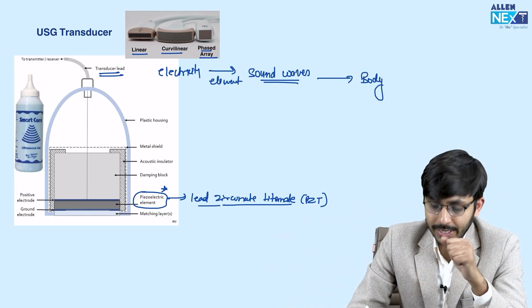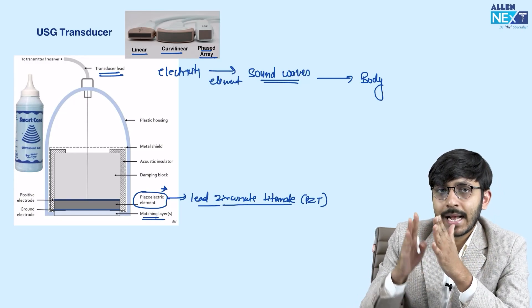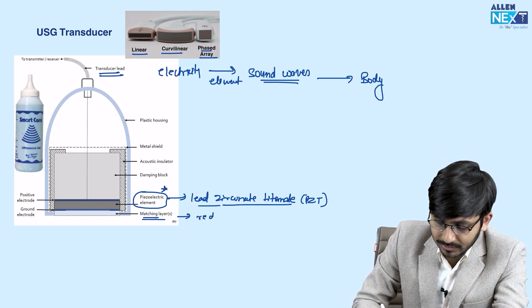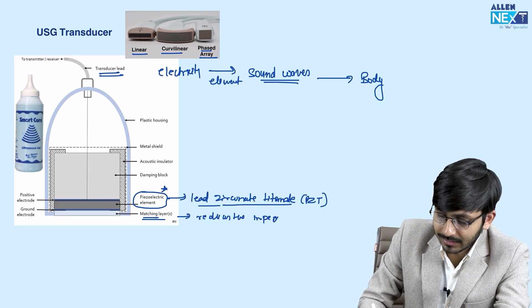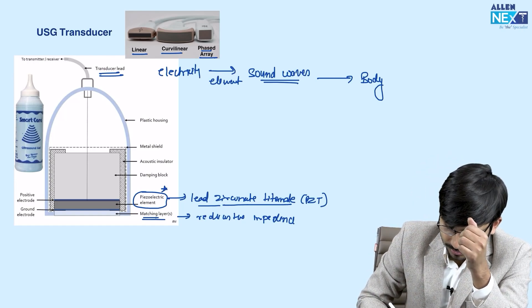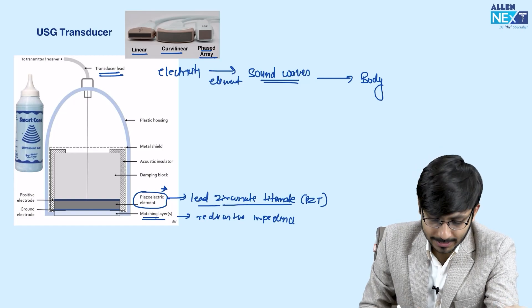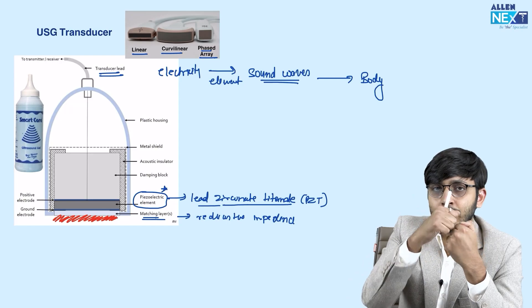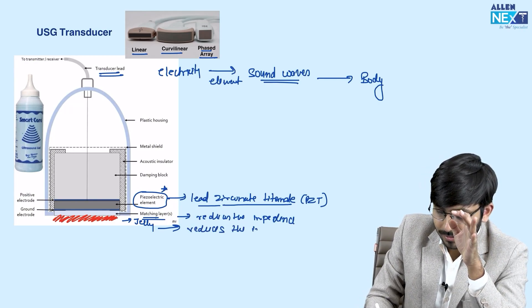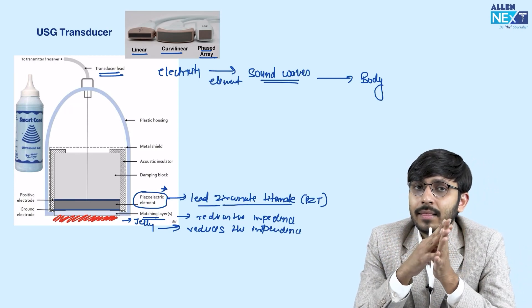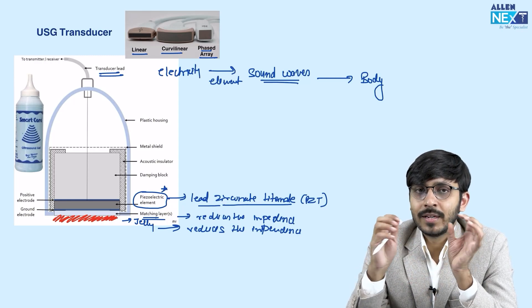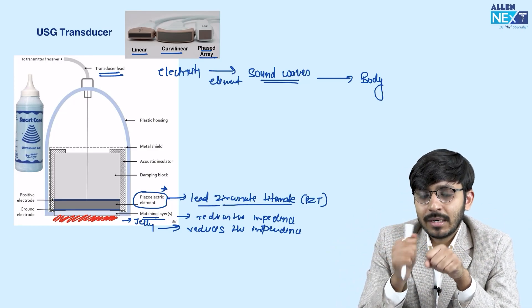These sound waves are transmitted through the body. There is a matching layer between the piezoelectric element and the surface of the transducer. This matching layer has a density similar to the piezoelectric element and reduces impedance, so that sound waves travel efficiently without reduction in intensity. Similarly, the ultrasound jelly placed between the transducer and the body also reduces impedance — without it, air would act as a poor conductor of sound waves, reducing their intensity.